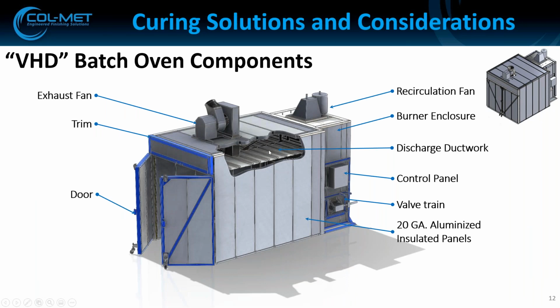Here's a cutaway, again, just giving you a better look at the discharge ductwork being in the ceiling of the oven. We also have our exhaust fan, which is a characteristic of all Class A type ovens that have to have an exhaust fan, again, because there's the possibility for having volatiles in the oven. One of the other differences with the VHD oven is that the burner box is not completely assembled. So when you receive it, the fan, the burner is mounted on a frame, and then you have to assemble the panels around it as you're constructing the oven. With the BO oven, the burner box is completely assembled and tested as one unit.